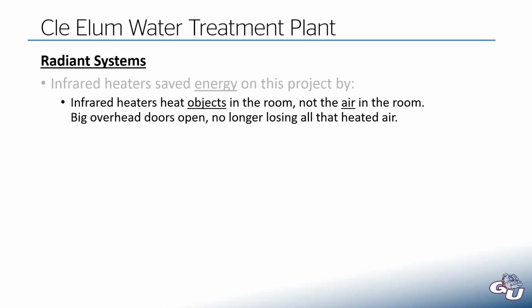At this water treatment plant, the radiant system heats all of the concrete floors, the pipe in that room, the walls, and the stairs directly. That means when they open the big overhead doors, they're not just losing a rush of heated air, because it's a lot harder for those warm objects in the room to lose their heat energy just because a door was open for a couple minutes. When I say heated, I don't mean hot to the touch, but they are much warmer compared to a standard fan-forced system that just heats the air and tries to maintain air temperature.